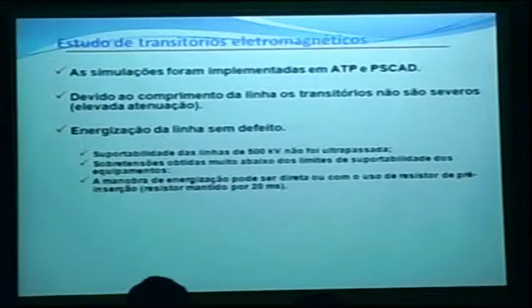We varied the number of generating units feeding the system. Initially, we were working with 3, and then we verified that it would be better to work with just 1 generating unit due to the setup of the substation. So we varied the number of generator units, and we also varied between direct energization without any methods, and then the pre-insertion circuit breaker of 400 ohms, which is the existing one, first with 8 milliseconds and then 20 milliseconds.